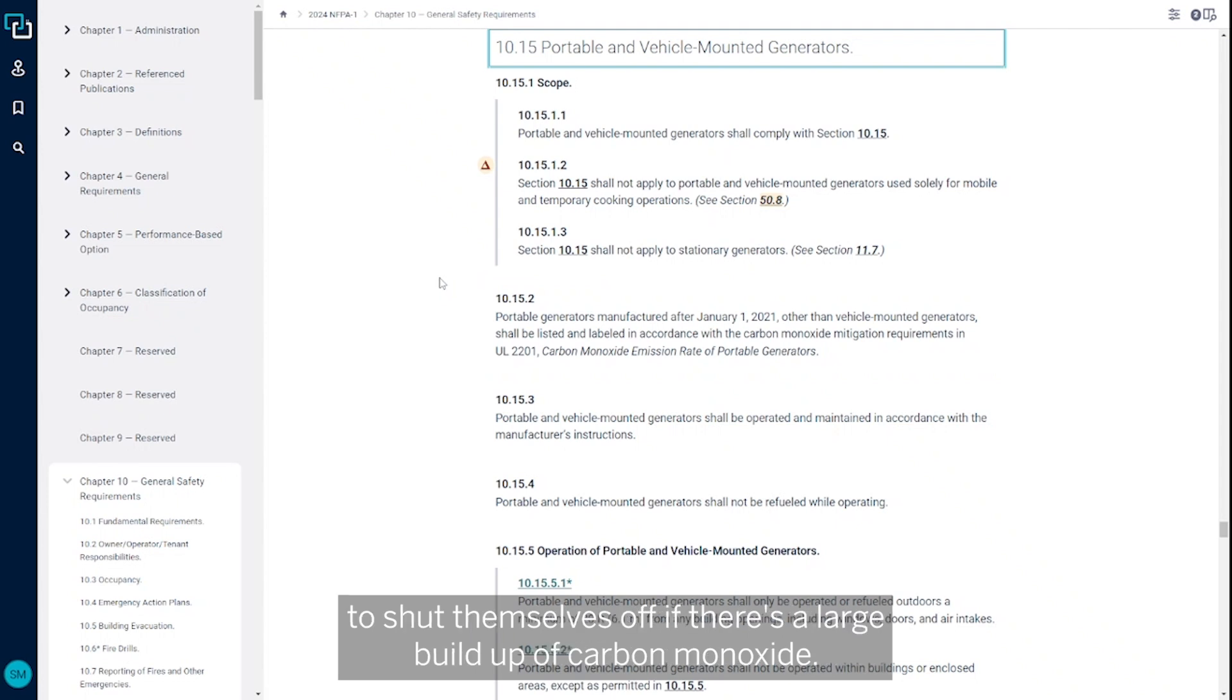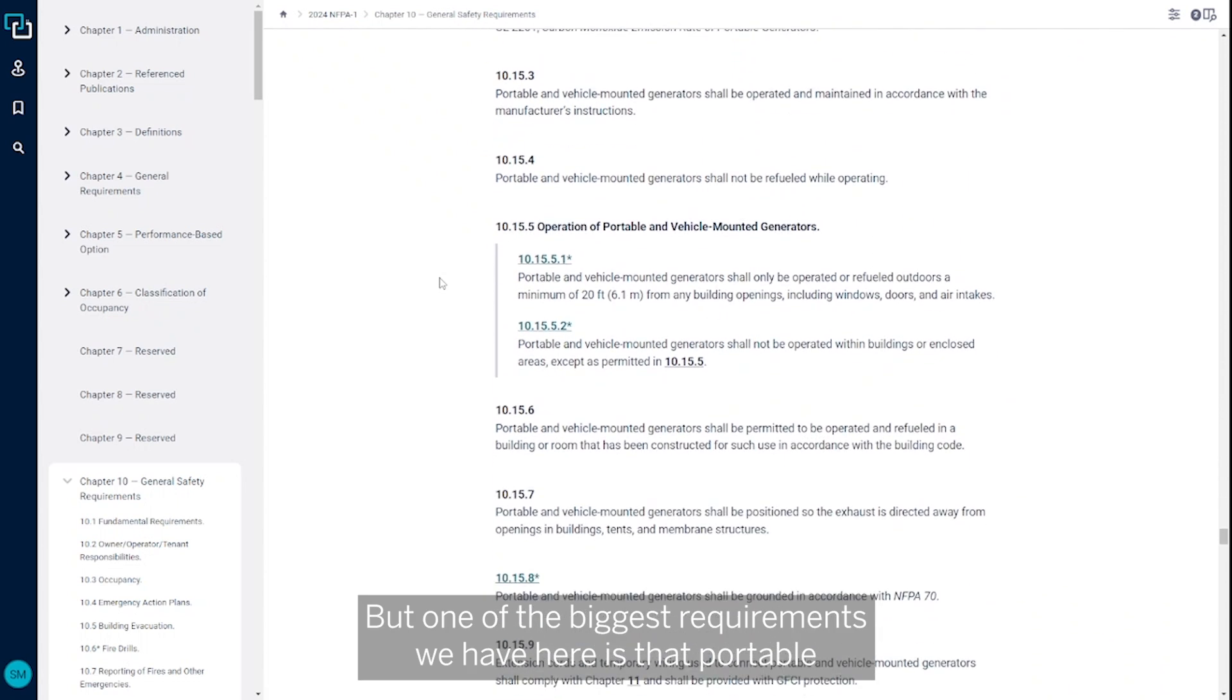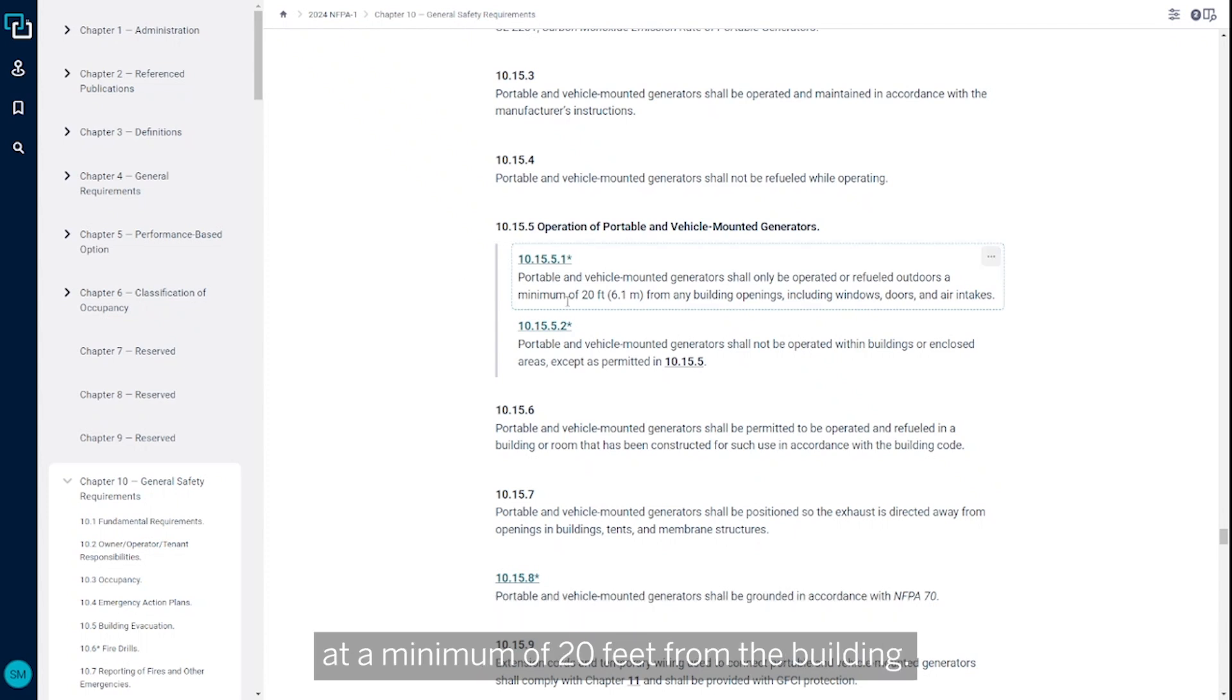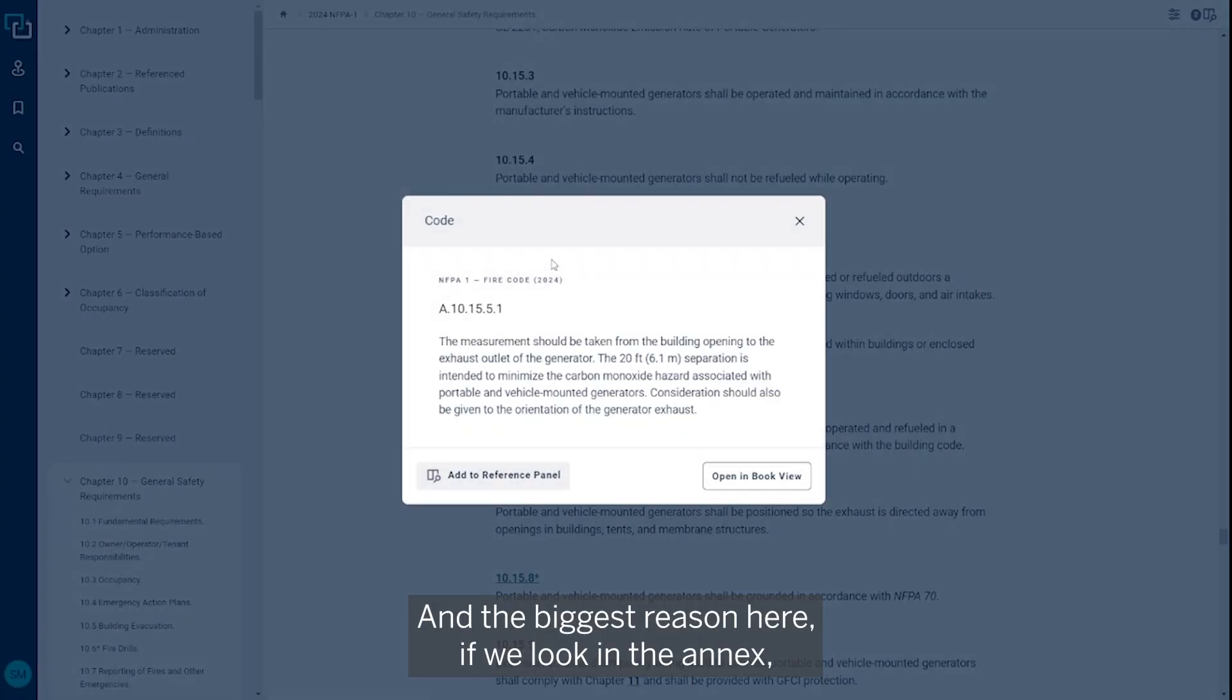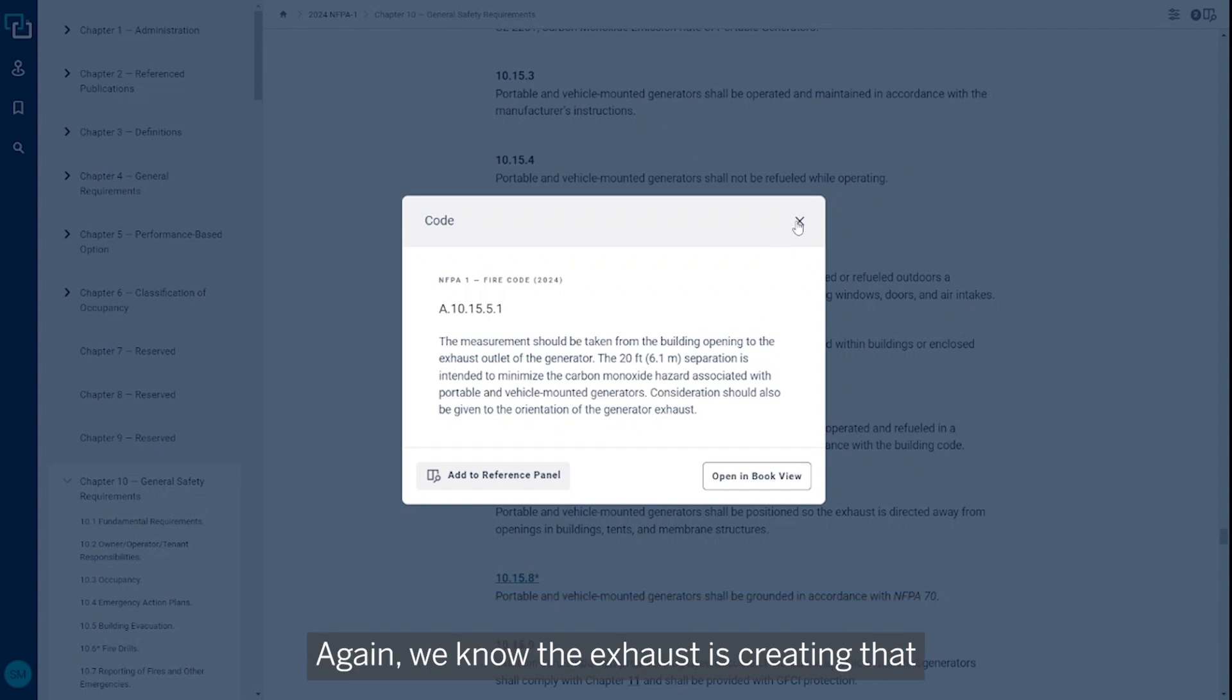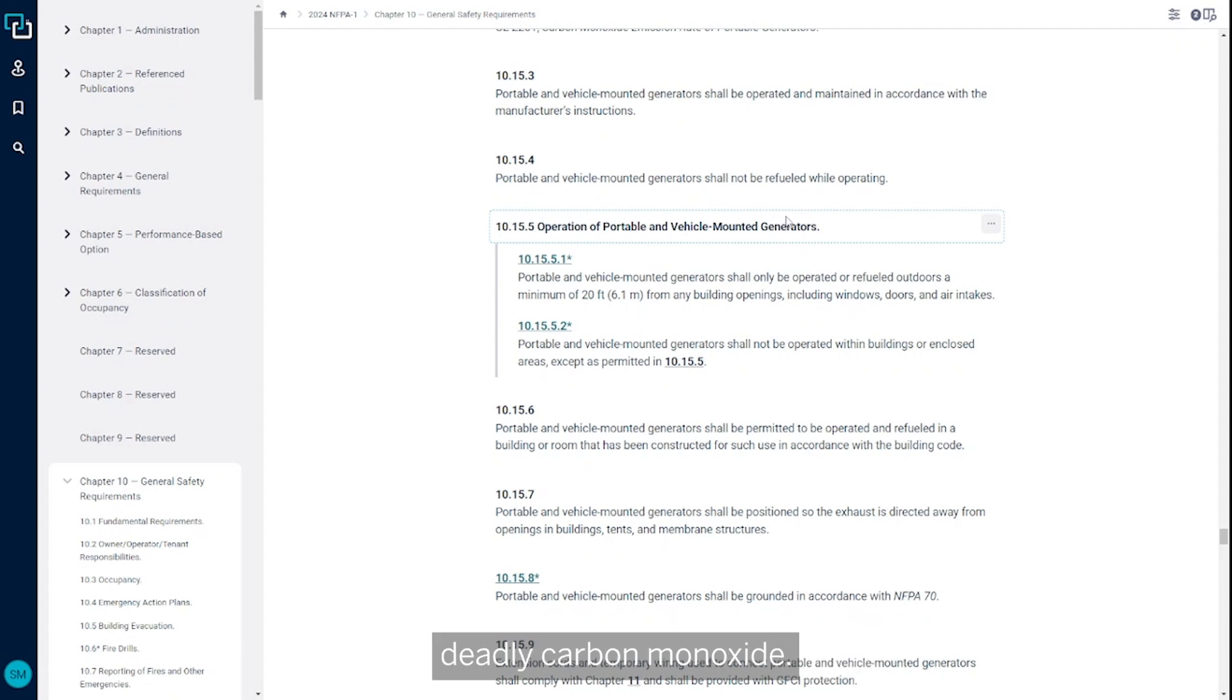But one of the biggest requirements we have here is that portable and vehicle mounted generators need to be operated and refueled outside at a minimum of 20 feet from the building. And the biggest reason here, if we look in the annex, the 20 foot separation is intended to minimize any of the carbon monoxide hazards associated with these portable generators. Again, we know the exhaust is creating that deadly carbon monoxide.